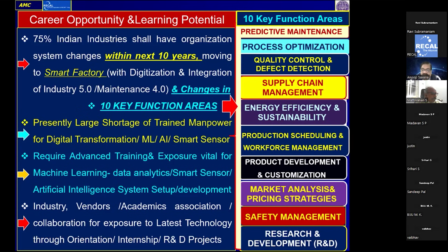But you are rightly saying 9 months is the minimum for ROI. We got it immediately because that particular machine was very dependent on product quality and the temperature variance of the billet going into the mill. There are sudden load changes and the effect of cooling and heating phenomena which damages the machine, which we were not able to capture with the offline monitoring we had in the plant.